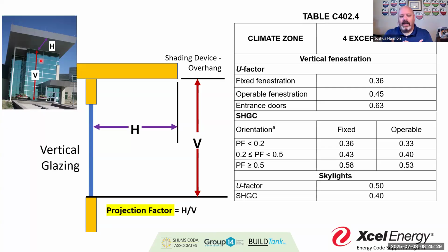And so you need to do one of two things: either take them off or contact the engineer and see what we can do to modify it. I'm okay with the modification if the engineer approves it, but that may affect other things. Ultimately the engineer came back and said, no, change them. That's going to affect the mechanical system calculations. We're not going to put in a brand new system, we've already ordered it. So it was a large conversation that took place because of window selection and the proper installation.